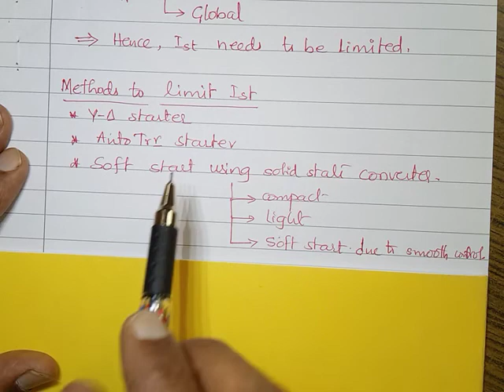Okay, and what are the different methods of controlling the starting current? We have star delta starter, we have auto transformer starter, and then we have the soft start using solid state converters. Star delta starter is very simple, but it is in steps, only one change, whereas auto transformer starter is a very good starter. You can change very smoothly, but it is very bulky, weight is more. Whereas using solid state switches, we can have the soft start using the converters, and because we are using power electronic devices, it's compact, it's light, and it can be smoothly started, because we can have smooth control. Hence normally it is called a soft start. So there are different methods of controlling the starting current, and that's where we have different starters.